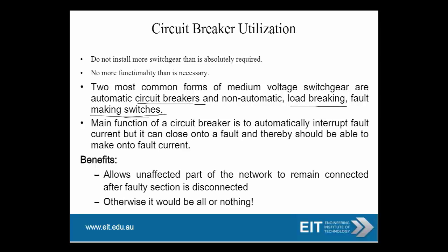The main function of a circuit breaker is to automatically interrupt fault current, but it can also close onto a fault and should therefore be able to make onto fault current. You might wonder why it needs to close onto a fault. You might assume the fault is cleared and turn on the breaker, but the fault might still be present. If the breaker is not rated to withstand closing onto a fault, it could get damaged. So a breaker must have the capacity to close onto a fault as well.